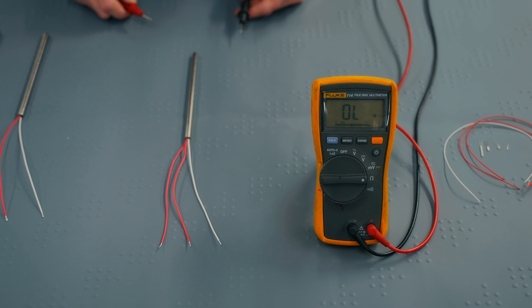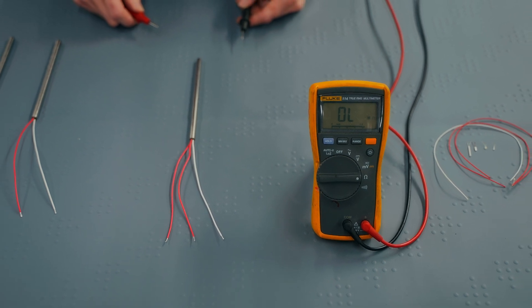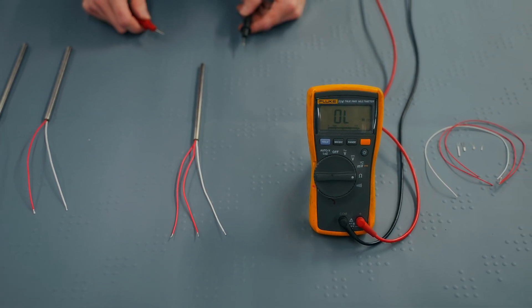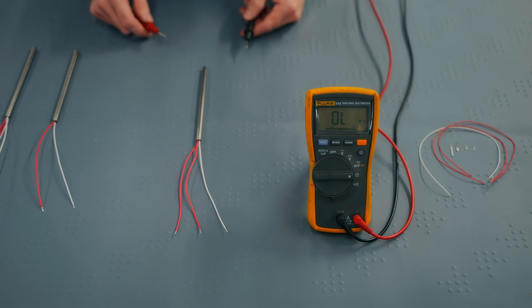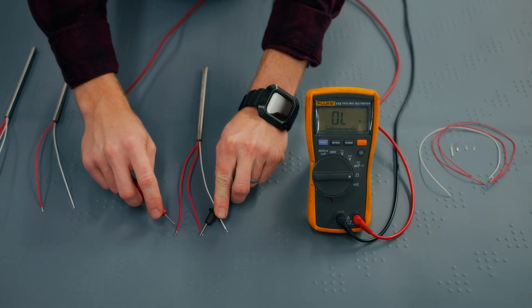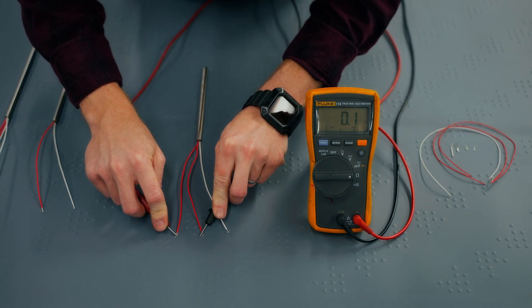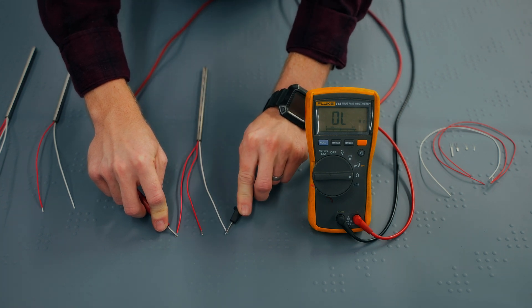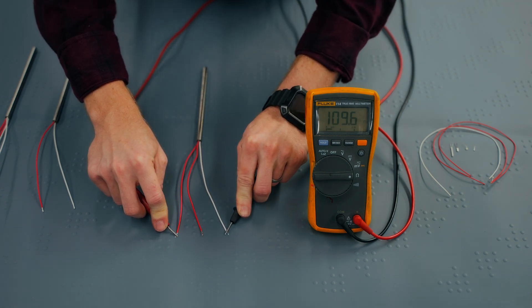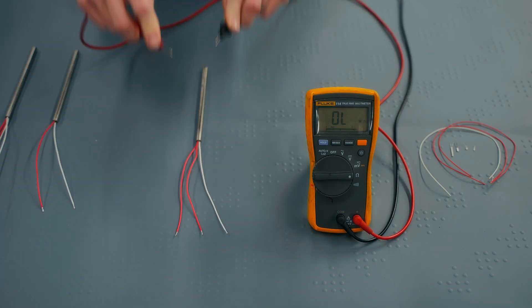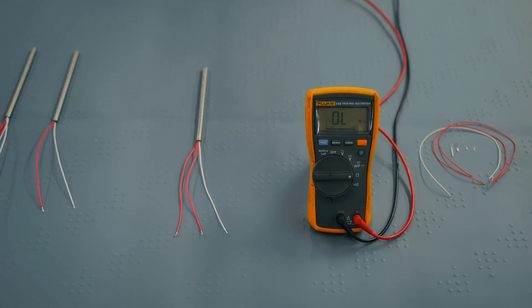On a three-wire RTD, two of the wires are connected to each other, and the third wire is connected to the opposite side of the platinum element. In general, these will be color-coded accordingly. Check the resistance between the two light color wires, and it should measure close to zero ohms. Then, check the resistance between the two dissimilar color wires. This RTD reads about 109 ohms, so it's functional.